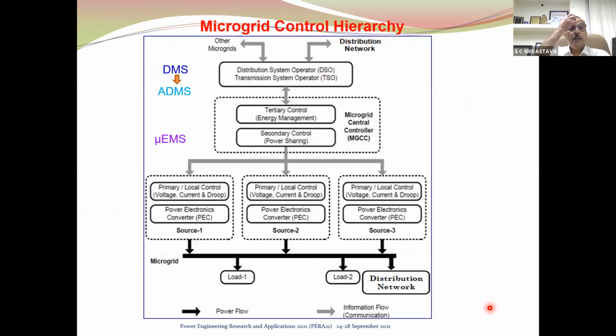Now, microgrids are provided with different levels of control. This is a very standard hierarchy. Primary control is the converter-level control, where you can also embed the droop control. Depending on the droop value, sources share the real power—like depending on the frequency droop, the conventional grid shares the power. It's similar to governing control.